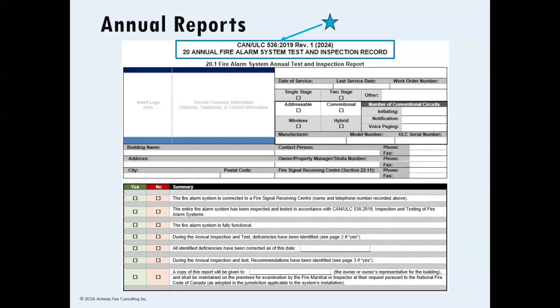Your system is also required to be tested under CAN-ULC S536 2019 Revision 1. You'll see I've highlighted that on the slide. This standard should be clearly indicated at the top on the first sheet of the report. If you are receiving a report that lists a different testing year, for example 2013 or 2006, fewer than 17 pages, or whose numbering appears to have fewer or skipped sections, it's worth checking to see if you've received the full inspection and testing required by the code.